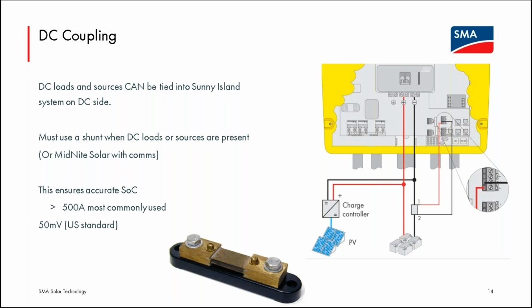And anytime there is something that touches the Sunny Island's battery bank outside of itself, the Sunny Island needs to know what the other thing is doing. Is it putting current into my battery bank? Is it pulling current out? Because it needs to update and adjust its charging regime to reflect that. So if something is touching the battery bank, a shunt, which is really just a high precision resistor that very, very accurately measures current, needs to be installed in line and wired into the Sunny Island.